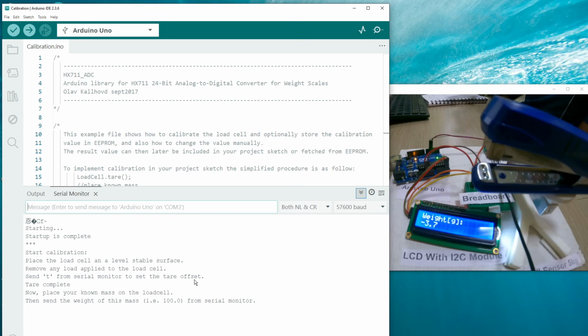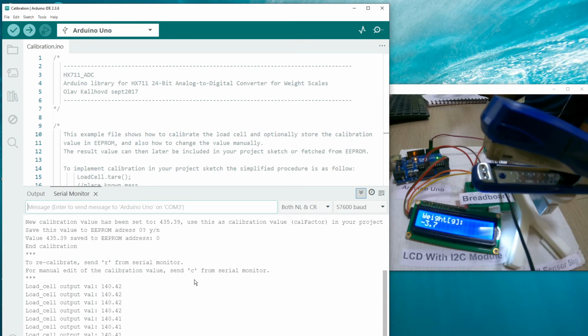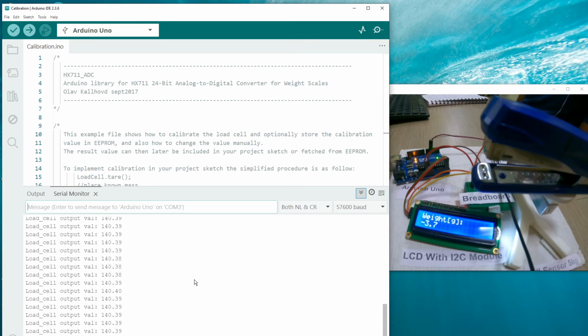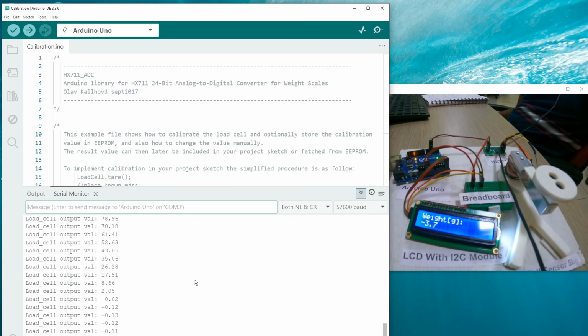So what I will do is I will enter 140.42 gram and enter. Once I enter the known mass, it has computed some calibration factor, 435.39, and then it is asking me whether this is to be saved to EEPROM or not. I will say yes, enter. Then it is basically displaying the weight. If I remove this, it has come to 0, meaning roughly 0.